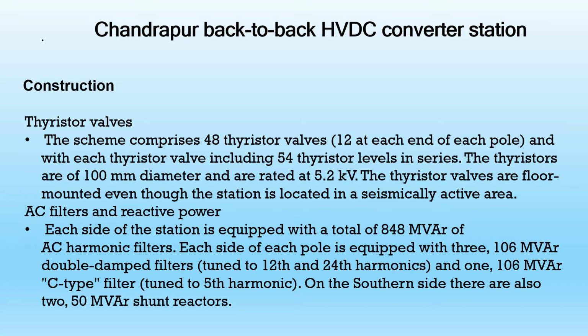Each side of the station is equipped with a total of 848 MVAR of AC harmonic filters. Each side of each pole is equipped with three 106 MVAR double damped filters and one 106 MVAR C-type filter. On the southern side there are also two 50 MVAR shunt reactors.